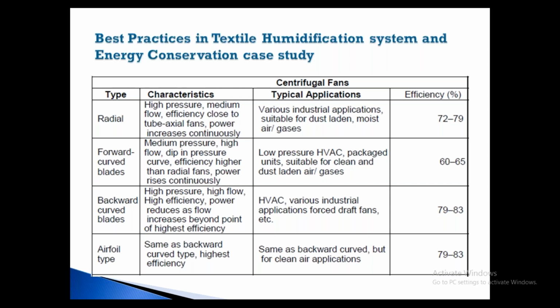So we consider this factor when we do the plant audit, as well as from the energy point of view. Plant audit means generally how the plants are working totally: what the maintenance schedule is, when they replace the filter media, when they change the blade angle, like that. All the data we collect, and also the data log. What RH do they maintain? They will tell you they try to maintain this. You ask for your data log sheet, then you will know. When you go for the meeting, they will just tell you they are maintaining this much, and in summer they are facing problems. If you collect the statistics, you have to collect the real time data, whether in the form of a computer printed sheet or, as they still do, written in the log book.